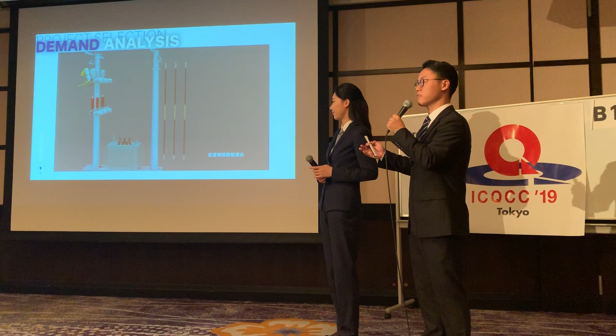But the lead-down equipment manufacturing and installation step takes 200 minutes, accounting for 38.5% of the total time. This step mainly includes 7 working procedures: cable cutting, cable insulation stripping, copper and aluminum joint installation at both end cables, cable bending and insulator binding, connecting the insulator and cables, installation of grounding rings, and final installation. All of them were carried out manually on the pole through on-site operation.